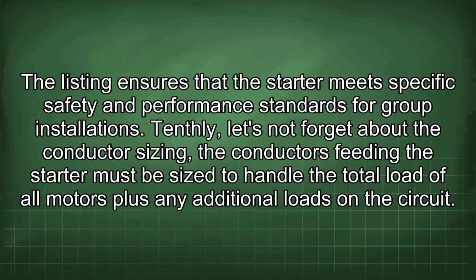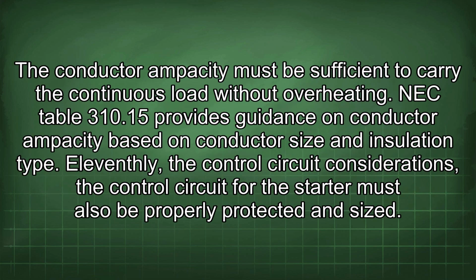10thly, let's not forget about the conductor sizing. The conductors feeding the starter must be sized to handle the total load of all motors plus any additional loads on the circuit. The conductor ampacity must be sufficient to carry the continuous load without overheating. NEC Table 310.15 provides guidance on conductor ampacity based on conductor size and insulation type.